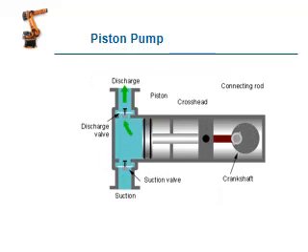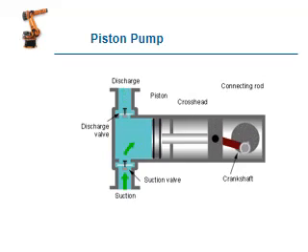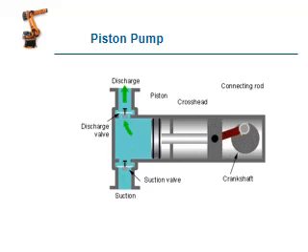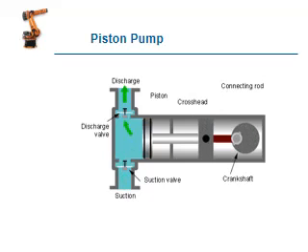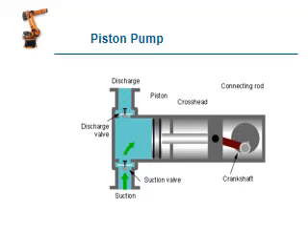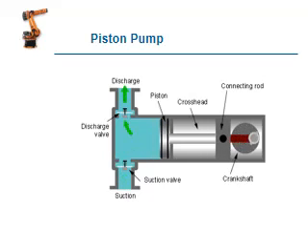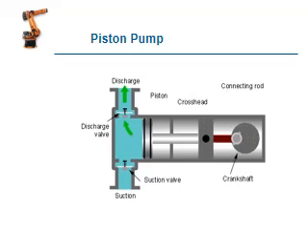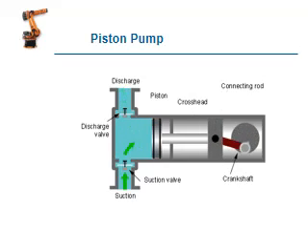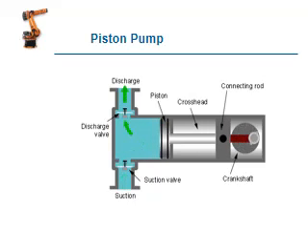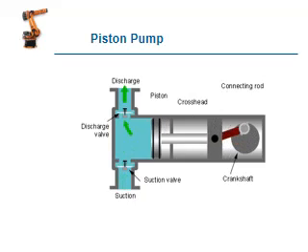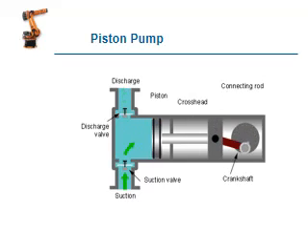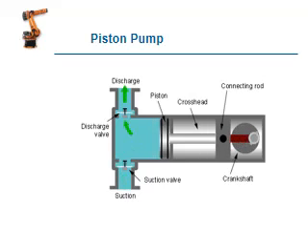So this is a piston pump. This slide shows the working principle of the reciprocating pump. If the piston moves from the left side to the right side, a vacuum is created there. Based on the vacuum creation, the oil from the lower level enters inside the piston. Then with further rotation, the oil pressure is increased from lower level to higher level. So it is discharged to the receiving place, like a direction control valve.